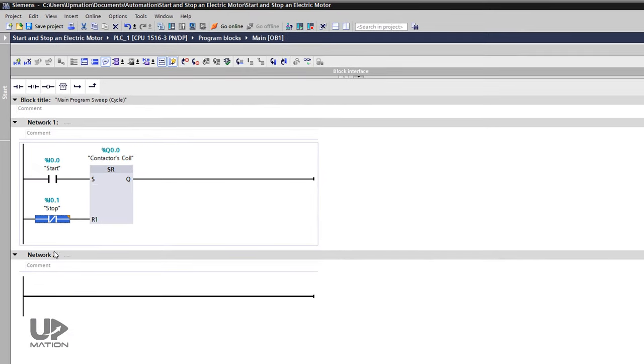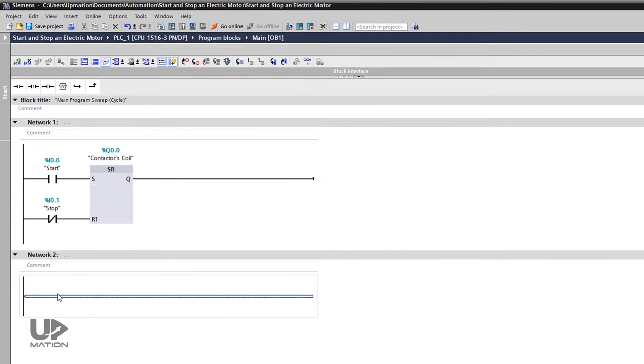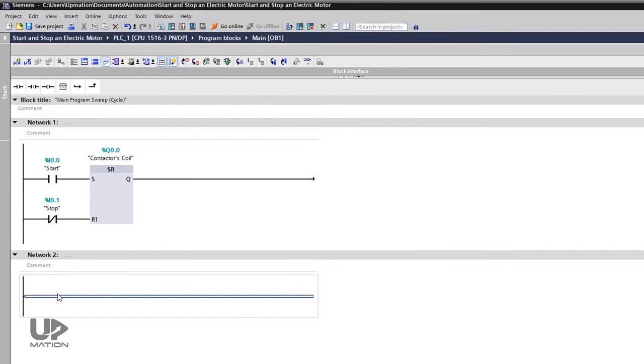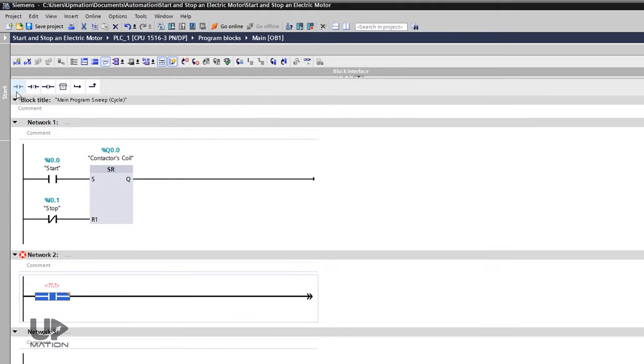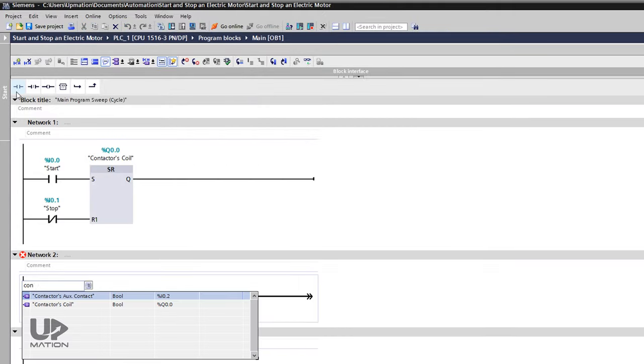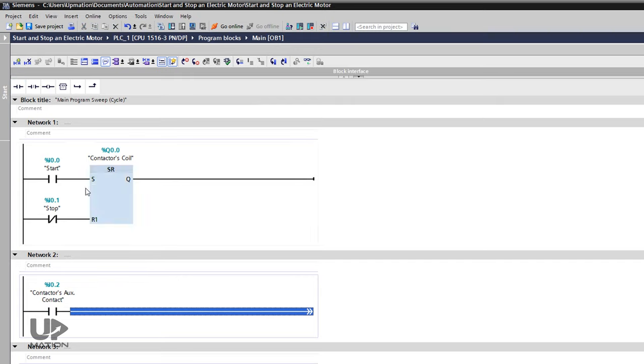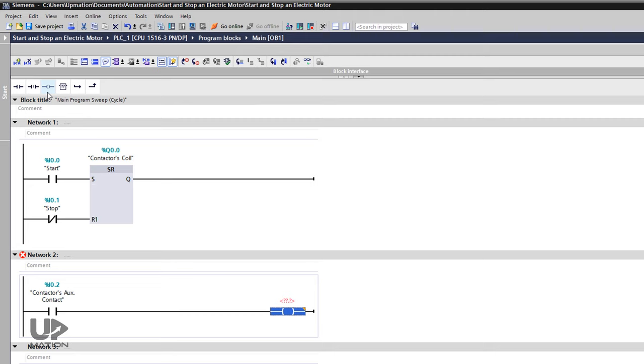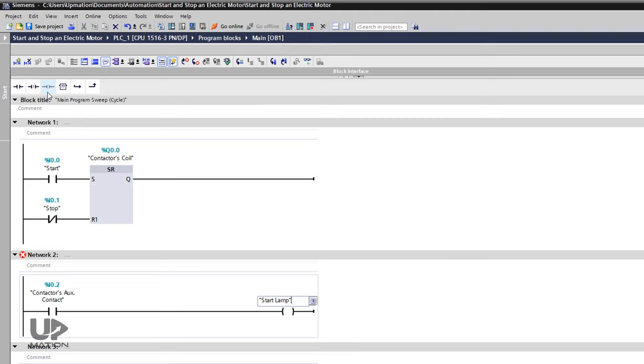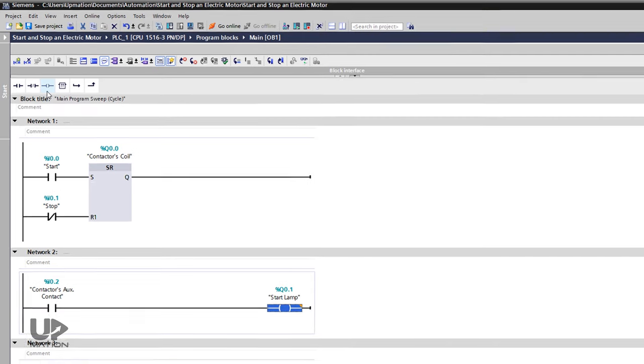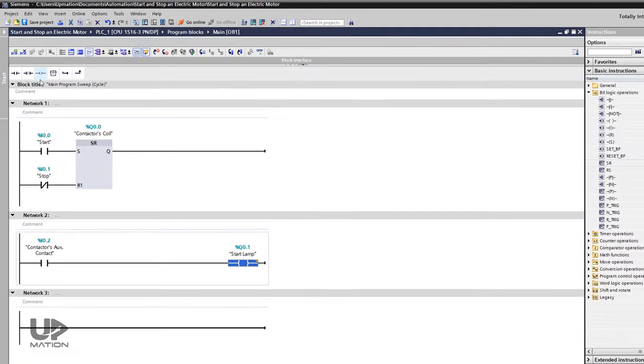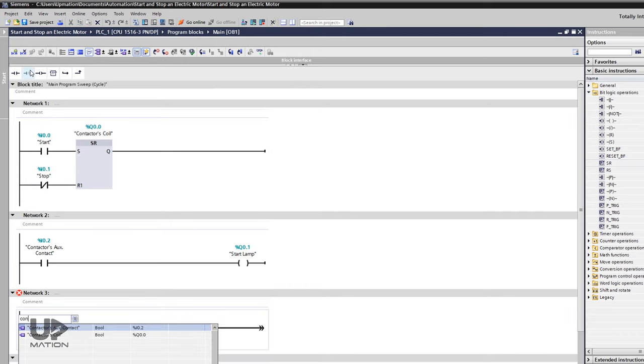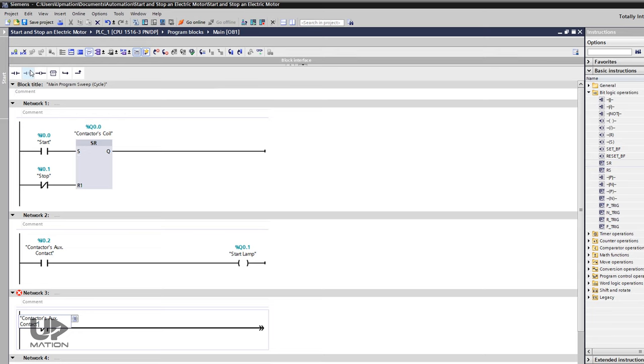I move on to network 2 to add the logic for indicator lamps. When the electric motor is not operating, the stop lamp should be on and the start lamp should be off. So here I need the NO contact of the contactor and I assign its input address to this open contact. Then I use an assignment or output contact for activating and deactivating the start lamp output. Let's do the same thing for the stop lamp. So this time I use a closed contact, but with the same address.